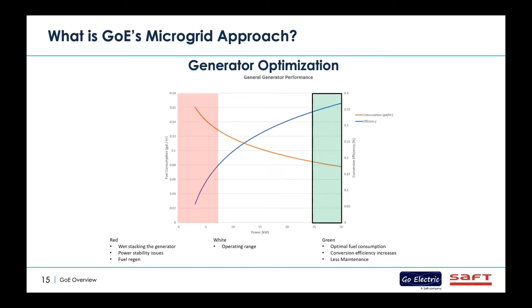This has a twofold benefit. One, you're running most efficiently, meaning you have the least amount of consumption used, which reduces your cost associated with diesel usage. It also reduces the cadence of maintenance needed, because you're not really using that generator anymore - it's more of a backup to the battery microgrid.